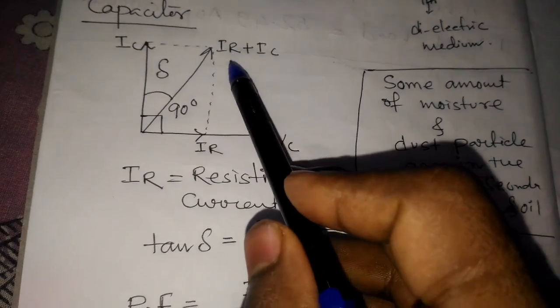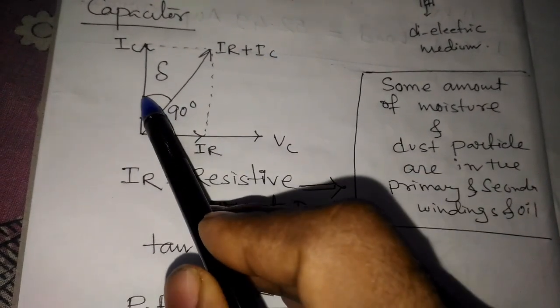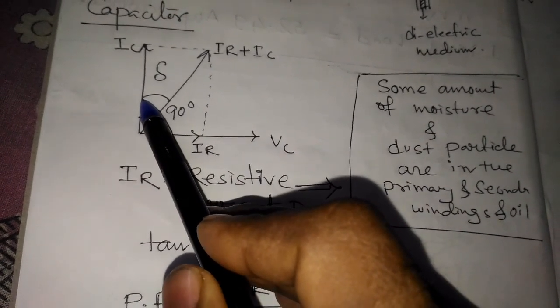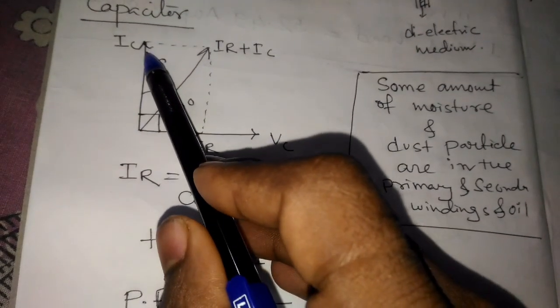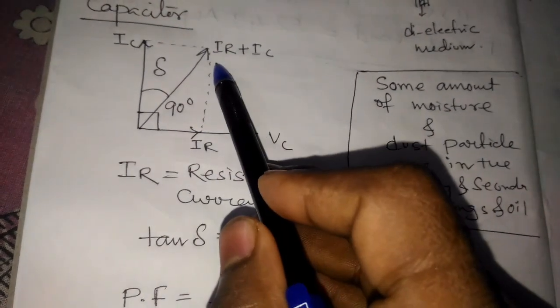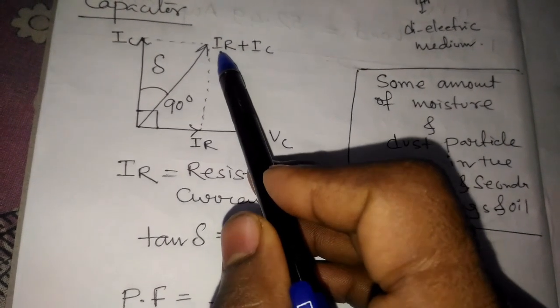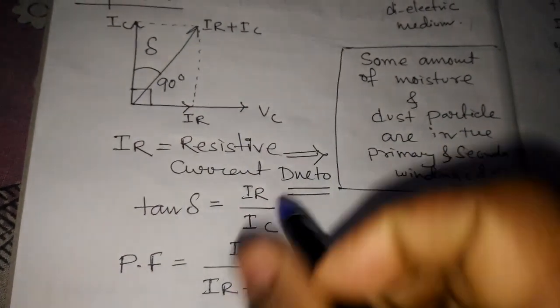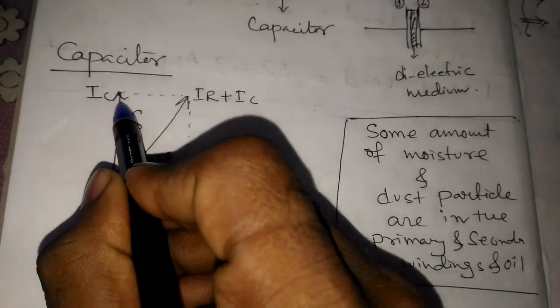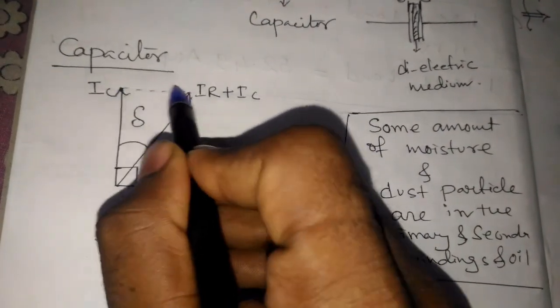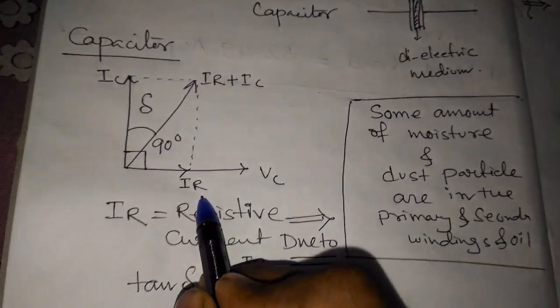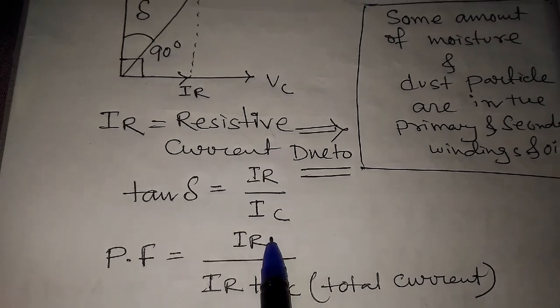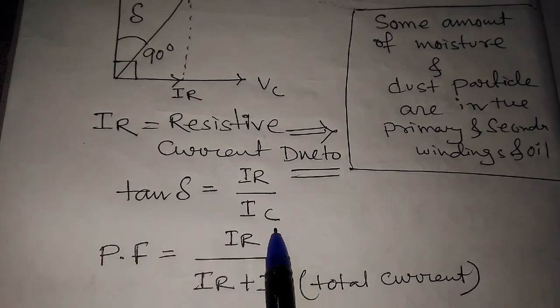When resistive current flows, the resultant current becomes IR plus IC. This delta angle deteriorates from the previous IC angle — that is the resultant current. This displacement is due to the resistive current. So Tan Delta equals IR divided by IC — resistive current divided by capacitive current.